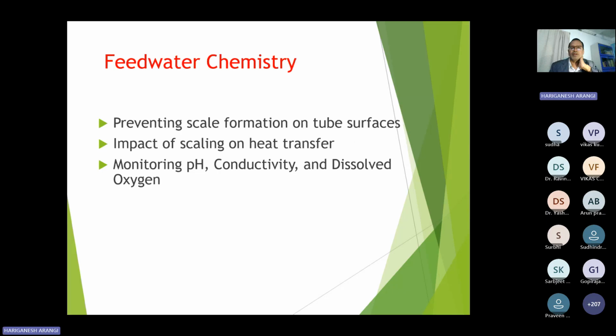Feed water chemistry plays the major role in any power plant. It is like the heart, because if you maintain the water quality in a proper way as per the standard design conditions, the turbines and boilers, which are the major equipment in touch with this water, will need no maintenance for a long time. If the water quality is bad, there will be scale formation, there will be punctures, and several other problems. For example, water parameters monitoring: pH, conductivity, and dissolved oxygen.